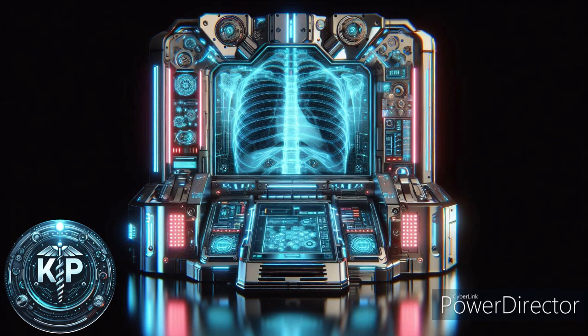Troubleshooting specific issues with the X-ray machine. When it comes to troubleshooting specific issues with an X-ray machine, a systematic approach is crucial. Let's delve into the steps you can take. Visual inspection: begin by meticulously examining the external components of the X-ray machine. Look for any visible physical damage, wear, or abnormalities. This initial inspection provides insights into potential issues that might affect the machine's performance. Timely identification of physical damage allows for prompt repair or replacement, preventing more significant problems down the line.